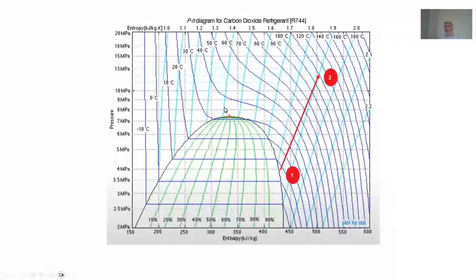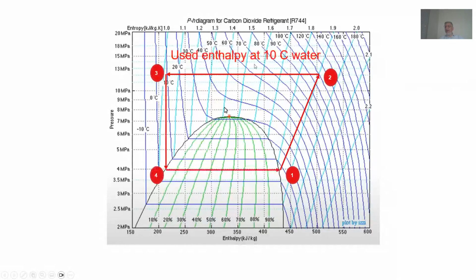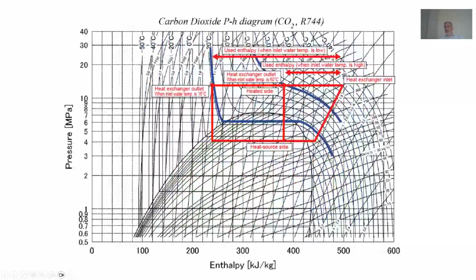But for the same compressor work, if your inlet water temperature is around 10 degrees centigrade, you have better heat transfer. Instead of water coming in at 60 degrees centigrade, where you stop the process here, now you are running more of the heat exchange process in the heat exchanger. So with the same compressor work, you get a higher output of hot water. In this kind of application it's preferred, and it is defined as a machine that does a high delta T but low GPM, because your capacity is constant.